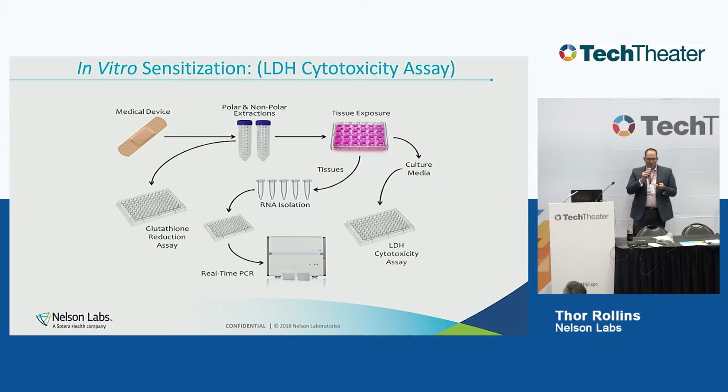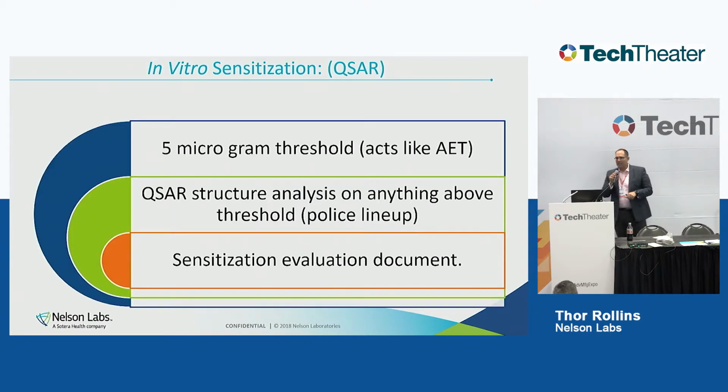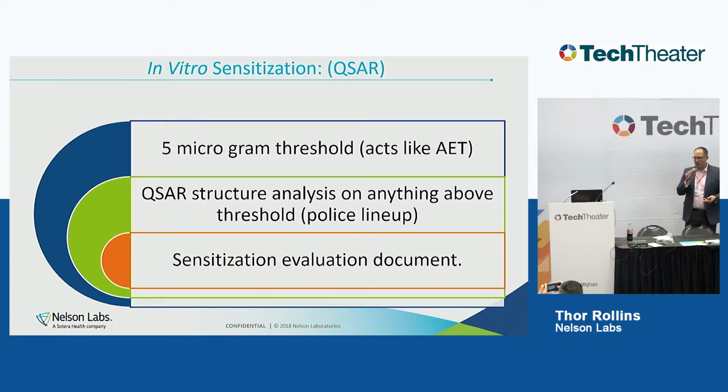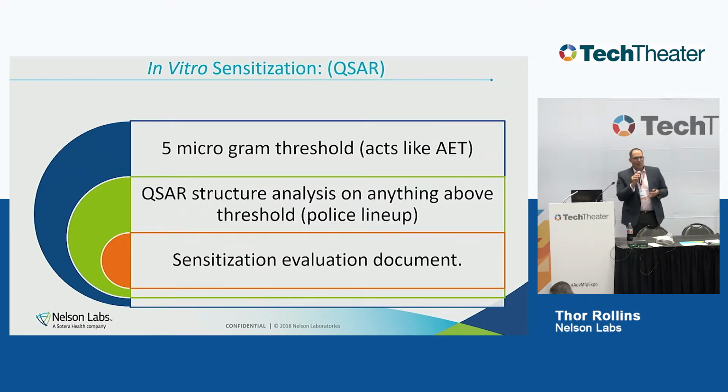The other component that we're looking at, which I really like, is using extractables and leachables to also evaluate sensitization. For those of you that may not be aware of extractables and leachables, it's a very hot topic right now, but basically we identify the chemistry coming off your device, and we identify and quantify those compounds.